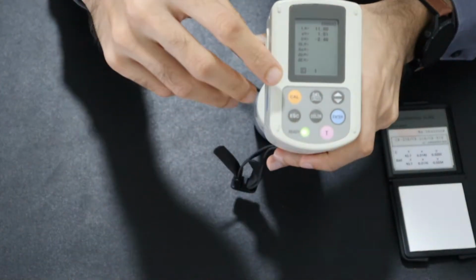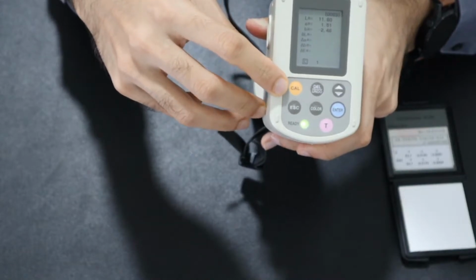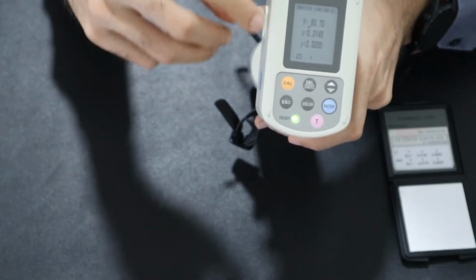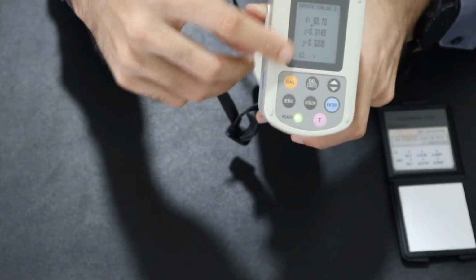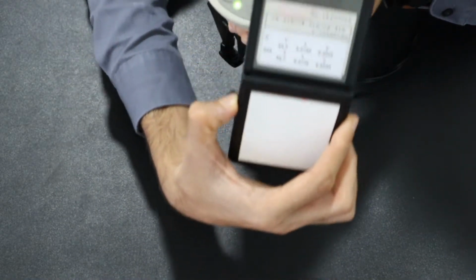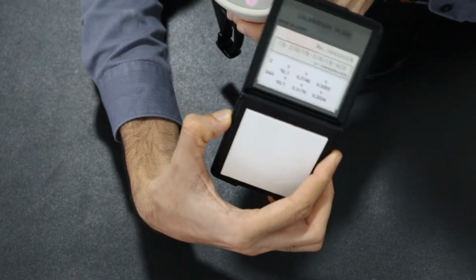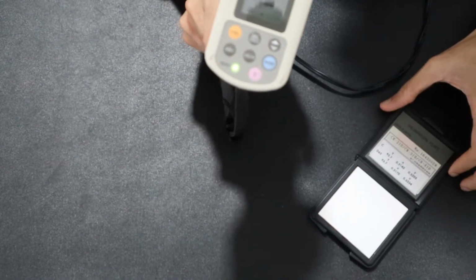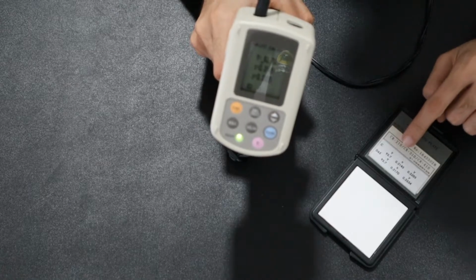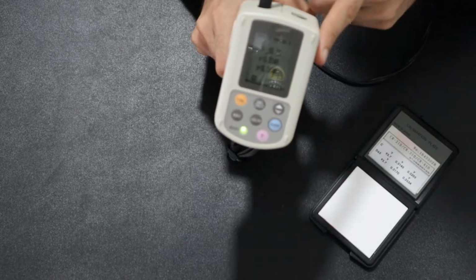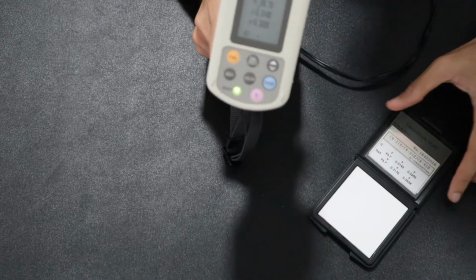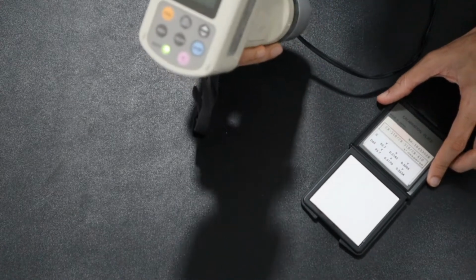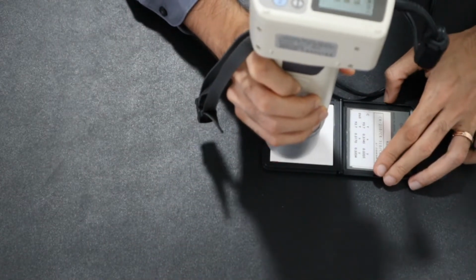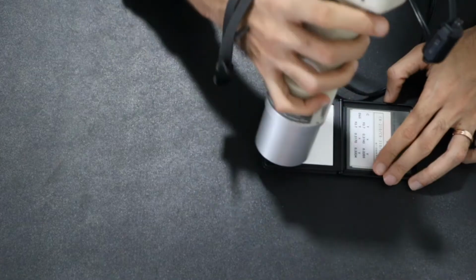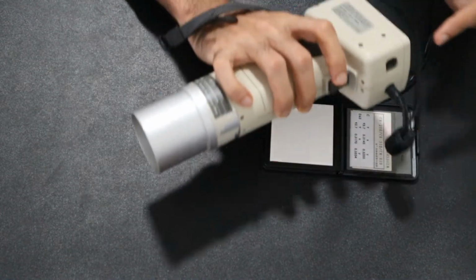So on the equipment, all I have to do is click the CAL button, the one in yellow. Okay. And I'll notice that the readings over here are similar to the one on the white calibration plate. Generally, once the equipment is calibrated, the readings on the white calibration plate should be the same as the readings on the CR-400 or CR-410 body. So the next step would be to place the equipment on the white calibration plate and press the measure button, which is this button over here.